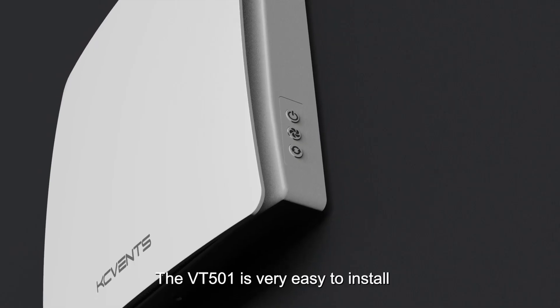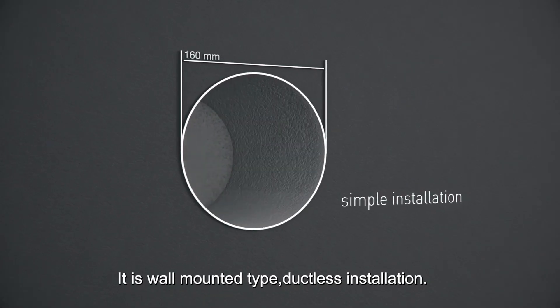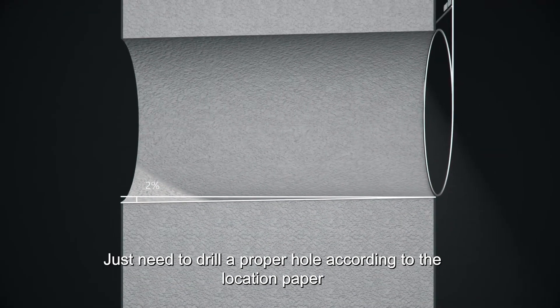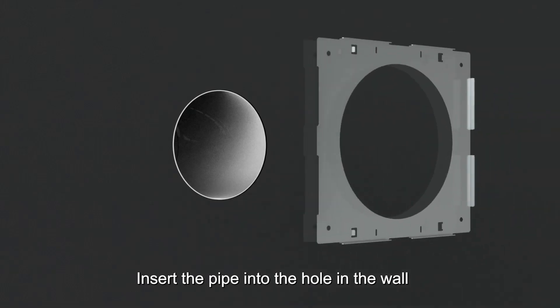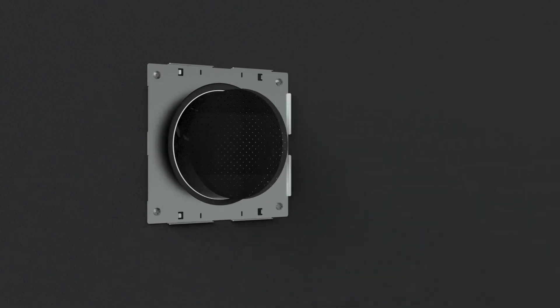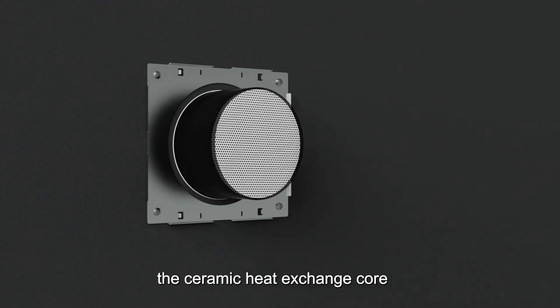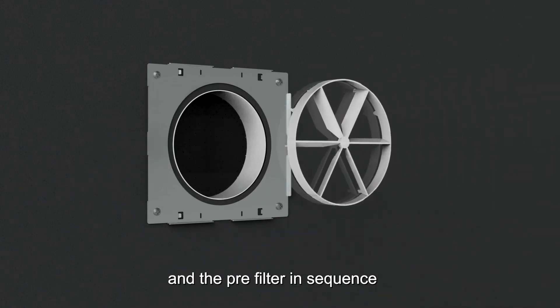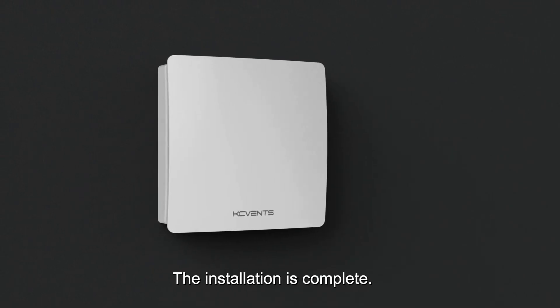The VT501 is very easy to install — it is wall-mounting, ductless installation. Just need to drill a proper hole according to the location paper, insert the pipe into the hole in the wall, and fix the iron plate. Insert the pre-filter, the ceramic heat exchanging core, and the pre-filter cover in sequence. Finally, install the panel. The installation is complete.